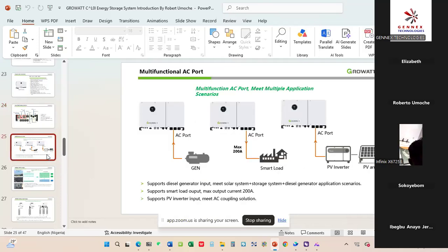Next slide. So here is explaining the AC port for the generator, the AC port for the smart load, and the AC port for grid inverter compatibility. We have the AC port the generator connects to, and the AC port the smart load connects to, which is the output of the inverter. The maximum current the system can have put together is 200 amps.